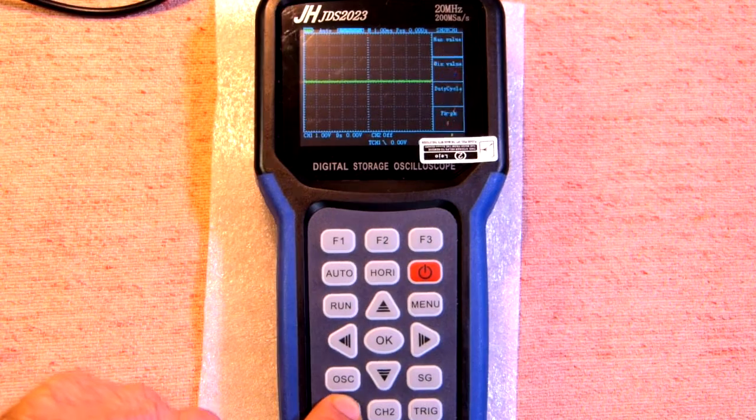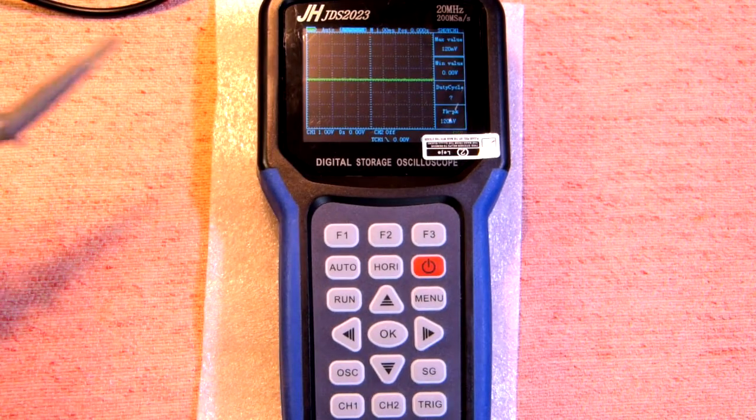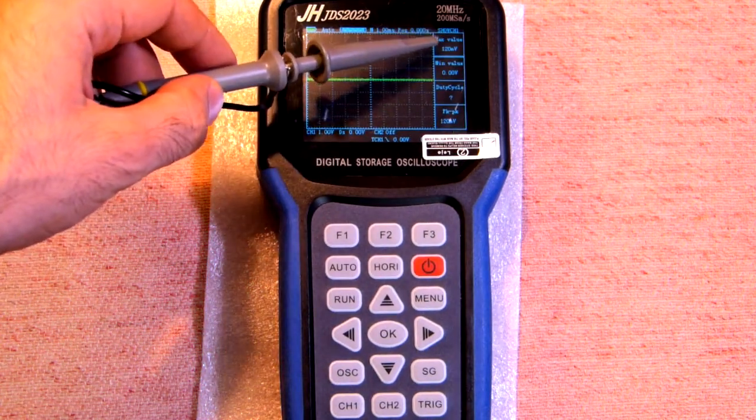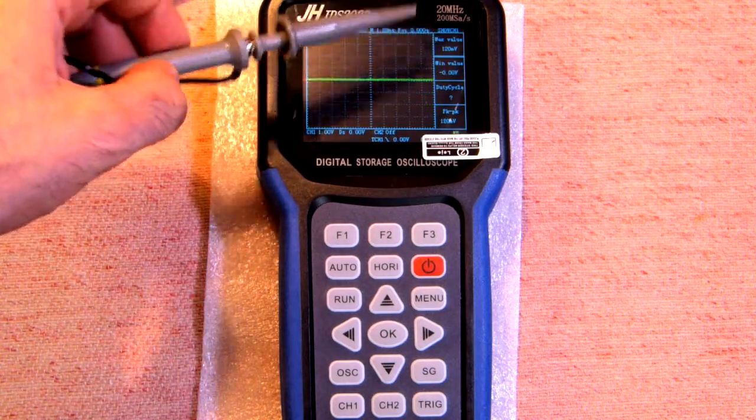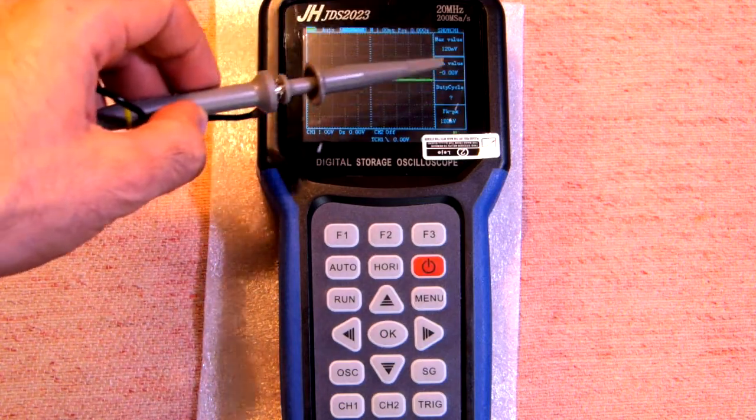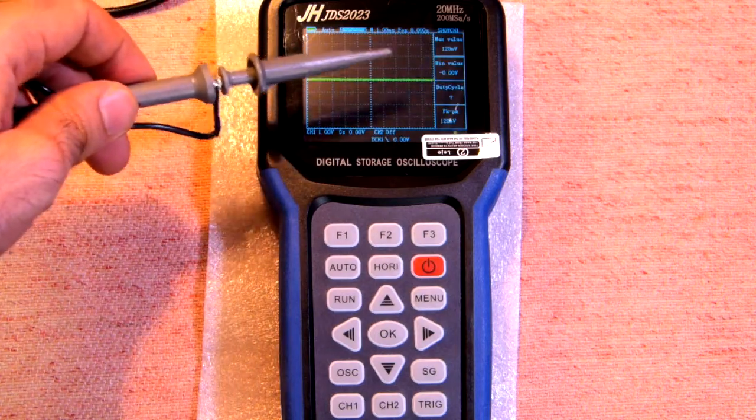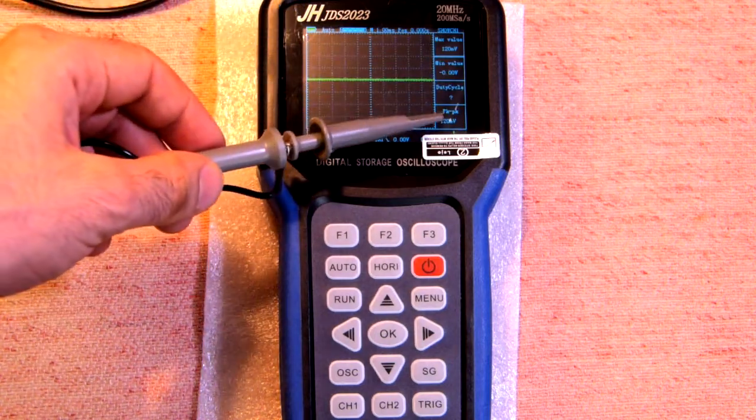The second pressing allows to measure the parameters. So here we have maximum value, minimum value, duty cycle if it's present and peak to peak level.